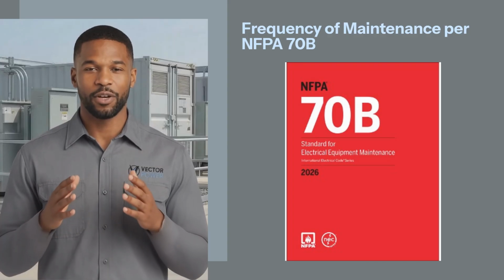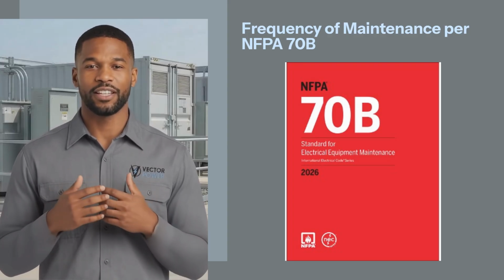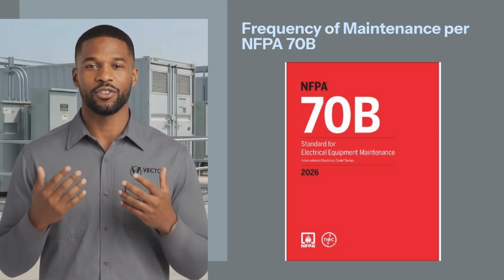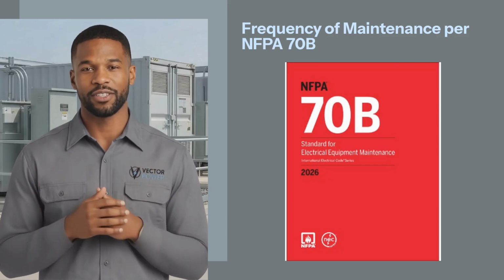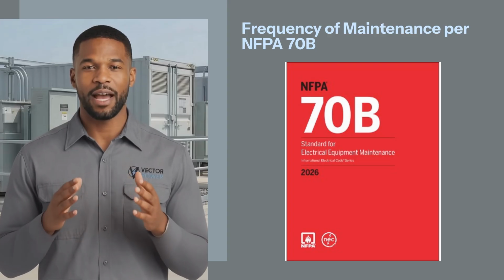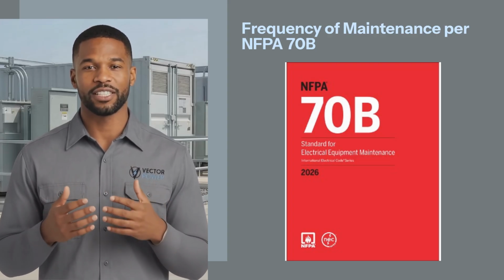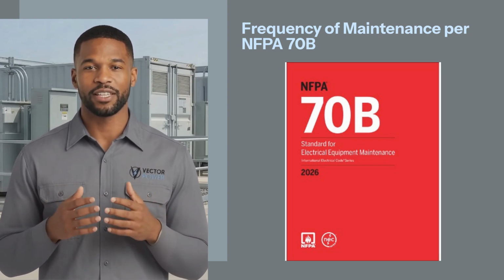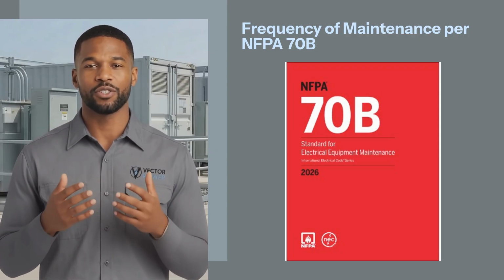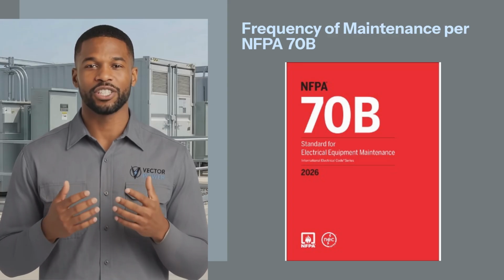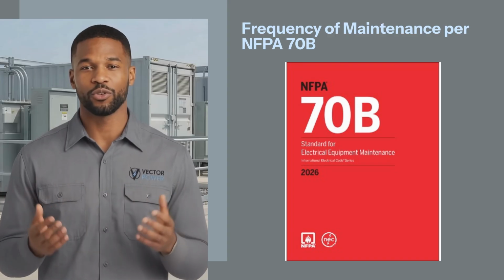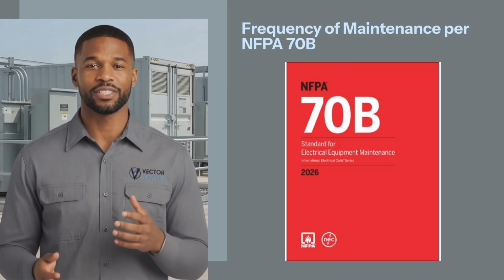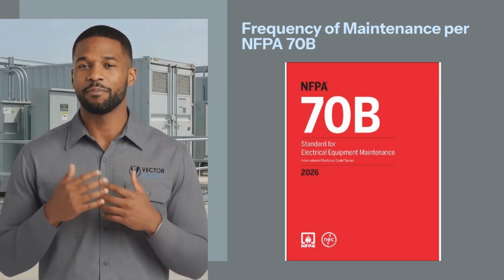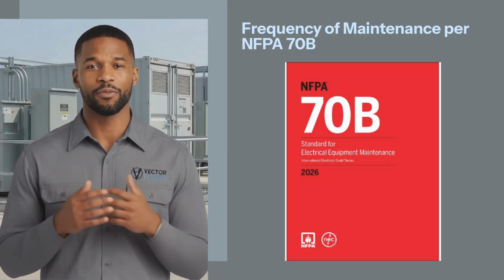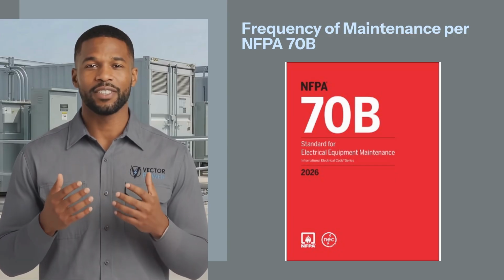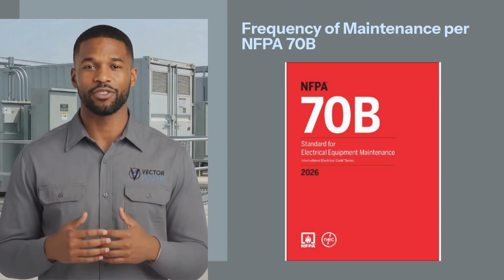Now, let's explore the maintenance frequency for battery energy storage systems. We will start with a general approach as per the NFPA 70B standard for electrical equipment maintenance. Later, we will take a deeper look by chemical type. According to NFPA 70B, if a manufacturer does not provide maintenance recommendations and if an equipment failure could pose an unacceptable risk to personnel or the environment, then maintenance must be conducted at intervals no longer than those specified in Table 9.2.2, which outlines maintenance intervals. In practice, for utility-scale battery energy storage systems, you almost always have original equipment manufacturer (OEM) instructions. NFPA 70B still matters because it makes maintenance a mandatory program requirement via an electrical maintenance program and provides a baseline when OEM guidance is incomplete, inconsistent, or not risk justified.